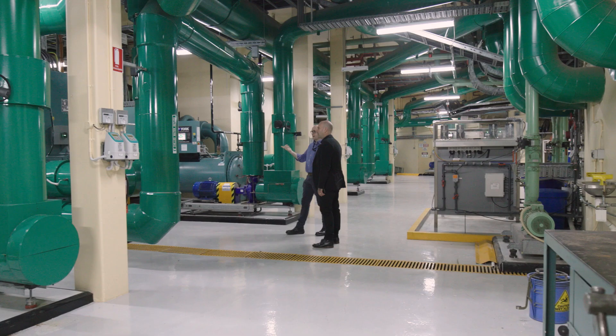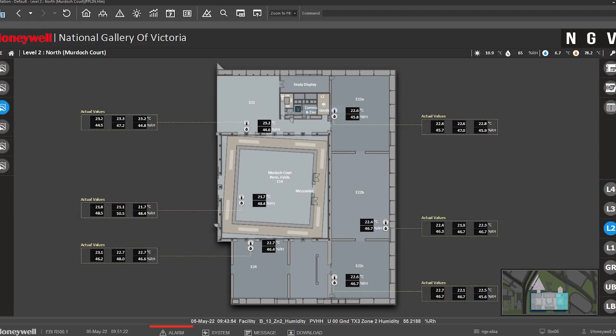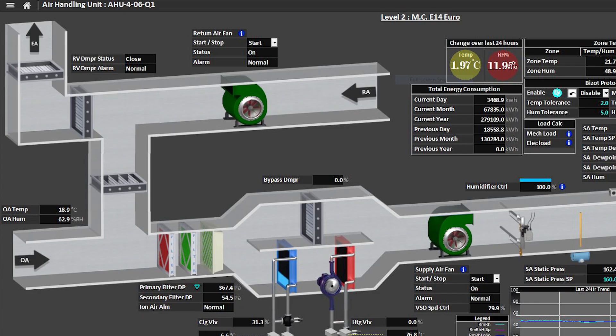Currently we are running a dual system in the museum. Some of our own collection galleries are running at Bizot parameters, and all of our exhibition loan galleries are not running at Bizot, so we've got this interesting middle phase where we're monitoring two types of things. The way we've been running this particular study is we've chosen a specific gallery that has a dedicated air handling unit. We've made some adaptations to the software and controls so we can switch on and off Bizot protocols from our more traditional tightly held protocols.